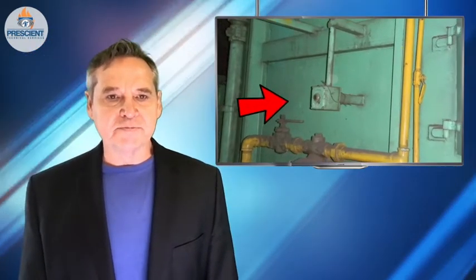He was attempting to light a furnace. He was standing there hitting the start button. What he didn't realize was that there was an accumulated flammable mixture within this furnace. It suddenly ignited, and an inspection door that was on a hinge right next to the start button swung open after the explosion, and part of it hit him in the head and killed him instantly.